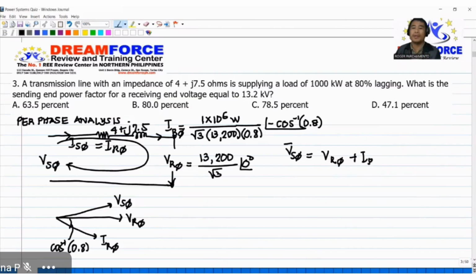Then plus IR per phase times Z per phase. So VR per phase, substitute. So we have 13,200 divided by square root of 3. Then plus the line current, 1 exponent 6 divided by square root of 3, from the 3-phase current formula times the line-to-line voltage 13,200 volts times the power factor. The angle should be included because we are adding and multiplying complex numbers. So multiplied by Z per phase, 4 plus 7.5 J.